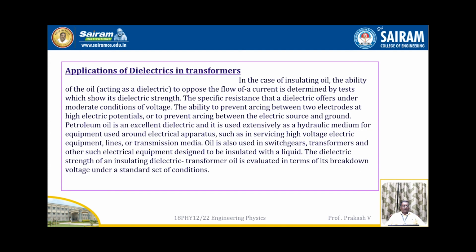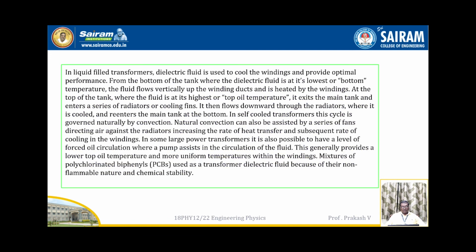And if we look at applications of dielectrics in transformers, in the case of insulating oil, the ability of the oil to oppose the flow of current is determined by tests which show its dielectric strength. Next, in liquid-filled transformers, dielectric fluid is used to cool the windings and provide optimal performance. From the bottom of the tank, where the dielectric fluid is at its lowest temperature, the fluid flows vertically up the winding ducts and is heated by the windings.